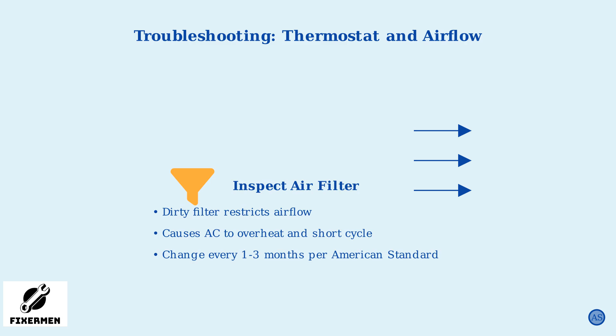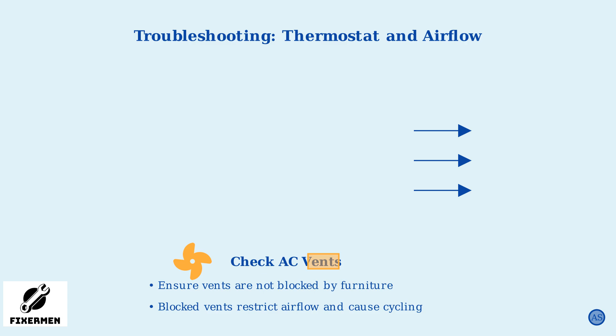Finally, check that your AC vents are not blocked. Furniture or other objects blocking the vents can severely restrict airflow, leading to the same overheating and short cycling issues. Make sure all vents are clear and unobstructed for optimal system performance.